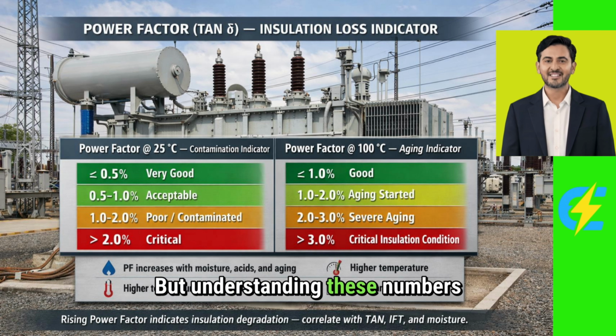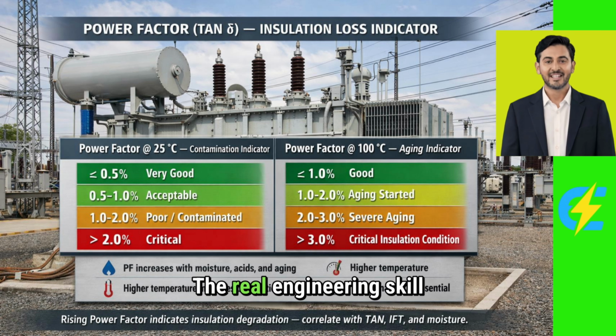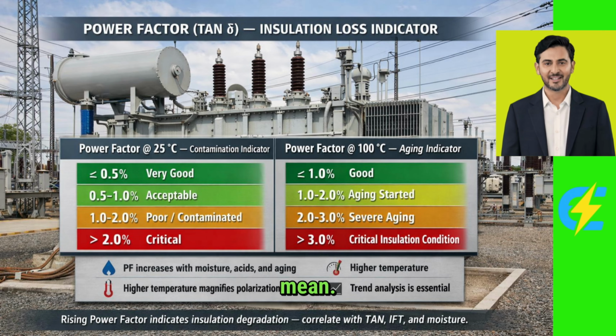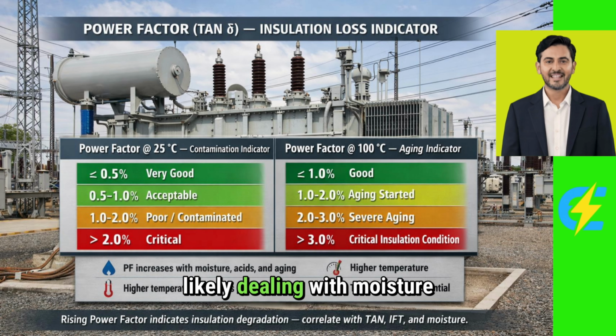But understanding these numbers is just the beginning. The real engineering skill comes in interpreting what different combinations of readings mean. If power factor is low at both temperatures, your oil is clean and in good condition. If it's high at 25 degrees but normal at 100 degrees, you're likely dealing with moisture contamination. If it's normal at 25 degrees but high at 100 degrees, this is very dangerous.